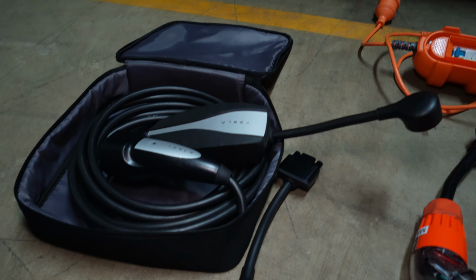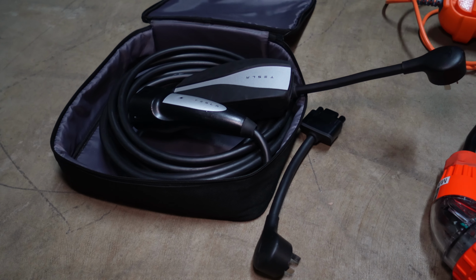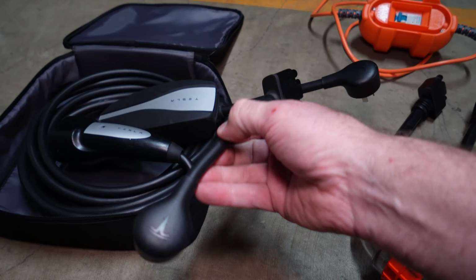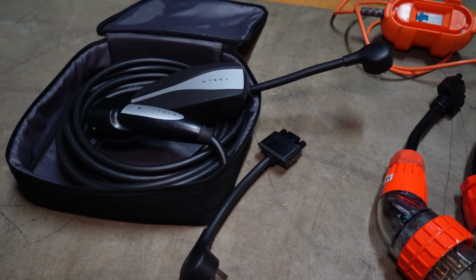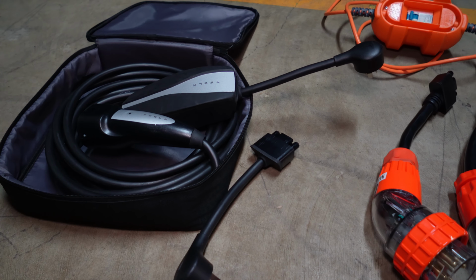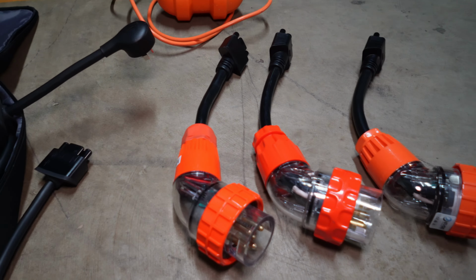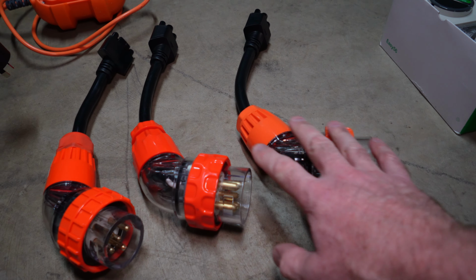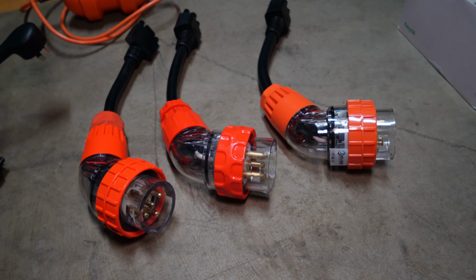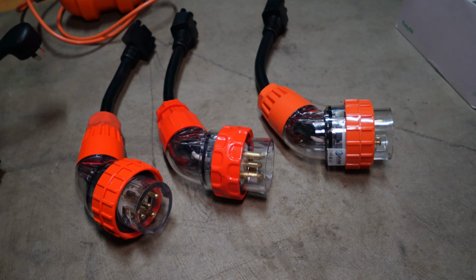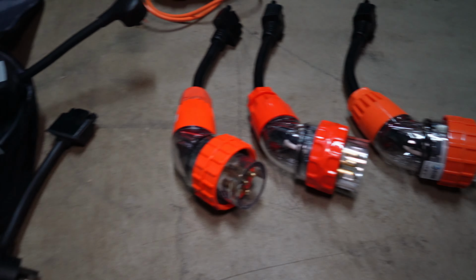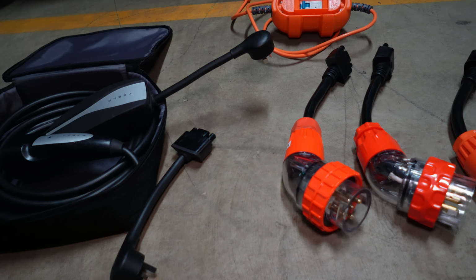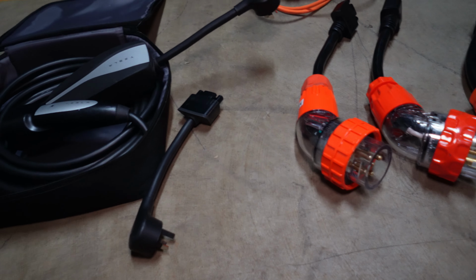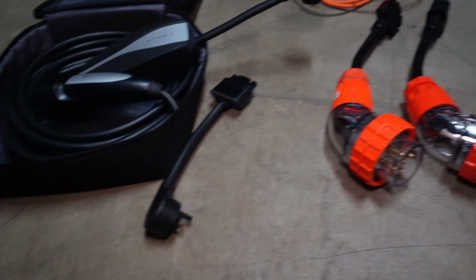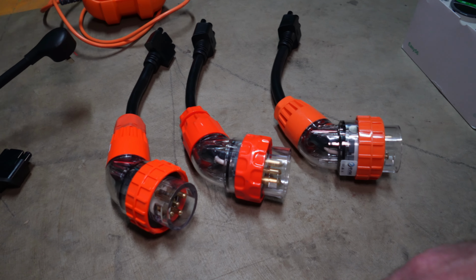So the UMC is managing that and communicating with the onboard charger or the BMS. The 15 amp tail will give me 3.6 kilowatts, the 20 amp tail will give me 4.8 kilowatts, and either of these 32 amp single phase tails will give 7.6 kilowatts. Basic electrical, you have to work out power, it's voltage times current, so 240 times 10 gives me 2.4 kilowatts, and so on.